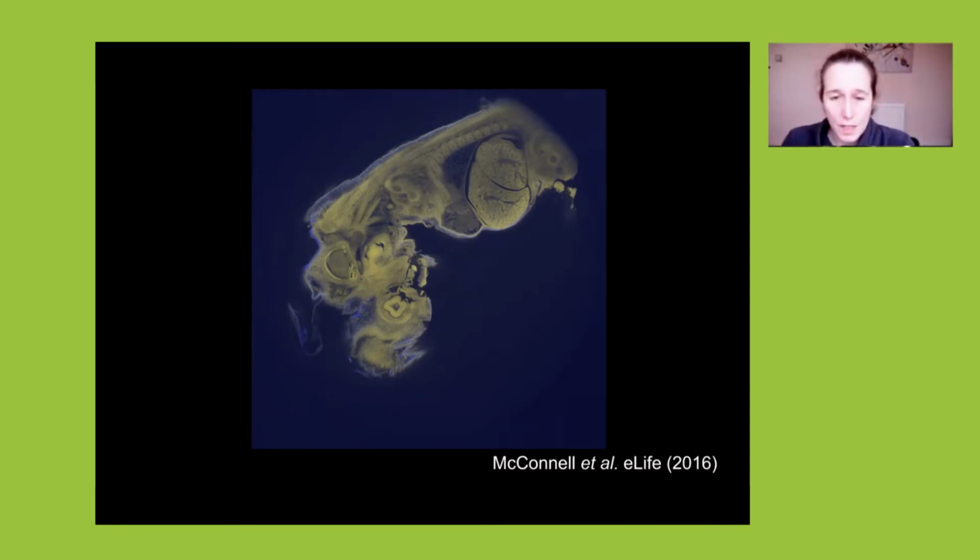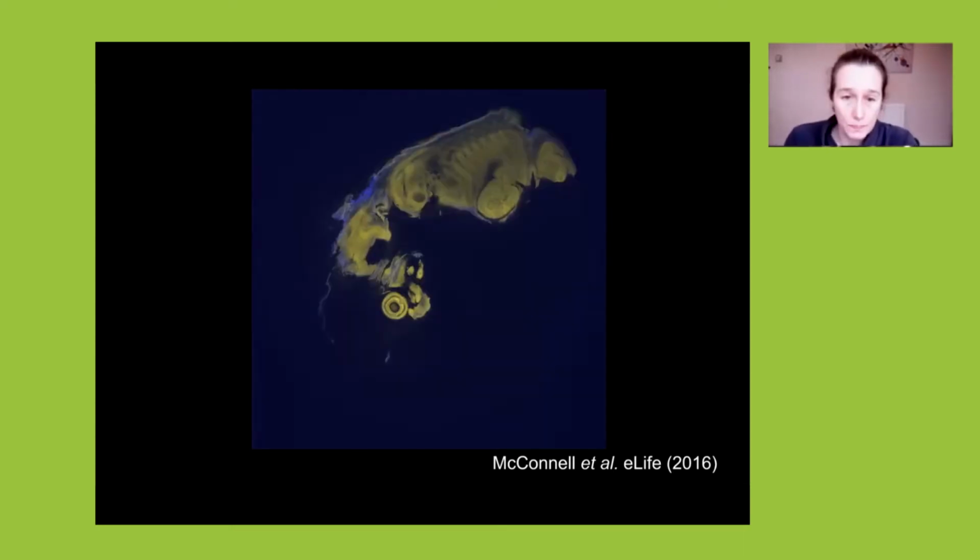Now is probably a good time to explain that the Mesolens is not a zoom lens. I realise that there are a bunch of manufacturers out there that will give you a stereo zoom macroscope, and they purport to give you a combination of low numerical aperture and high numerical aperture and low magnification. And they do, but they just don't do it at the same time, whereas the Mesolens does. We have a fixed relationship: we only have 4 times magnification, and we only have 0.47 NA. Any zooming that I'm showing you is entirely computational.